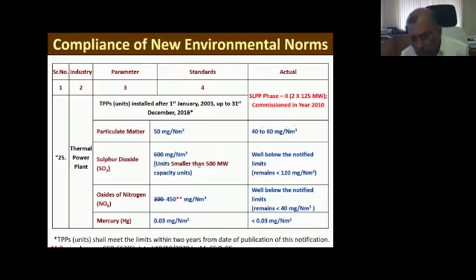I will show you the CPCB side details data also. Similarly, for SOx, though it is 600, we are achieving 120. For NOx, earlier it was 300, now it has been revised - this was discussed during the seminar also - to 450 mg/Nm3 under the new norms. We are achieving almost one-tenth of that, less than 40 mg per Nm3. And on the mercury side also, it is in compliance with requirements.